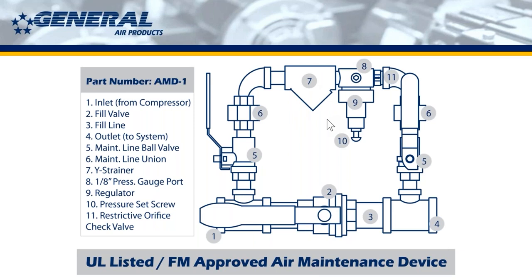So what we recommend is that if you do flip the orientation on installation for this unit, then turn the Y strainer so that this trap, the debris trap, is facing down and can catch that debris before it gets to the regulator. The regulator is again a restricted orifice.